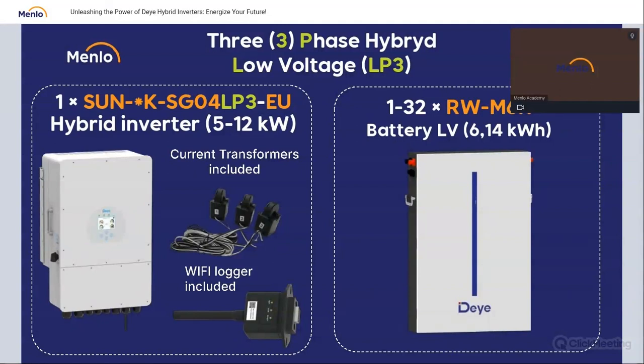And additionally, low voltage batteries are much cheaper. The inverter is more expensive, because if you want to reach the same power with lower voltage, you need to discharge with much higher current. It means that an inverter with low voltage batteries uses 60 square millimeter cables. It has to survive 200 amps of charge and discharge.